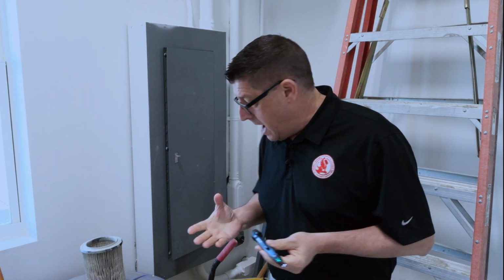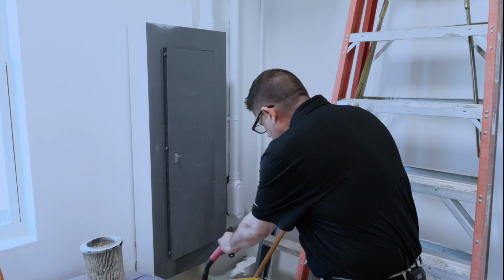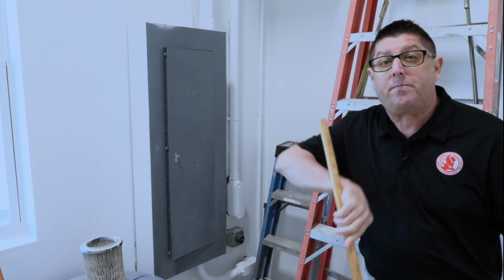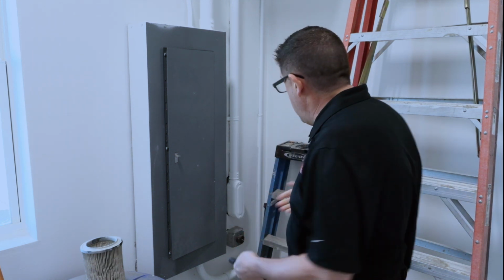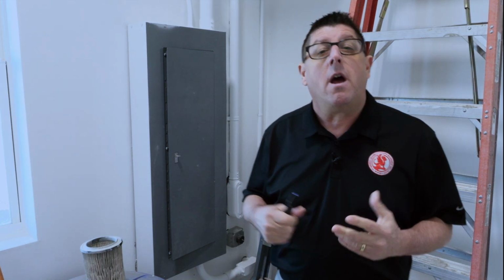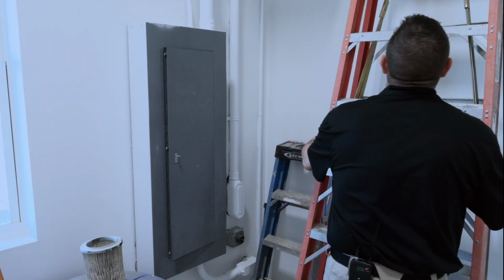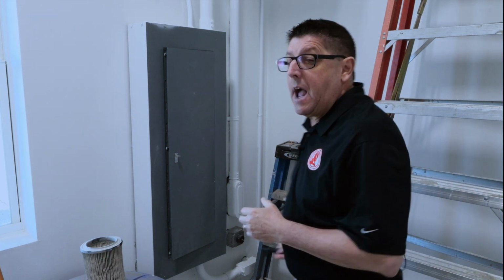Now, as a commercial property inspector, I would definitely take a photo of it, talk about encroachment into the working space, and recommend these items never be stored in front of the panel. But as a practical inspector, these are on wheels. I'm certainly going to move the mop bucket out of my way so that I can inspect. And if I can safely get in here around the ladder, I will do so. But in this particular case, I'm going to move this ladder as well, only because it's a very tall ladder and it's high voltage electric.